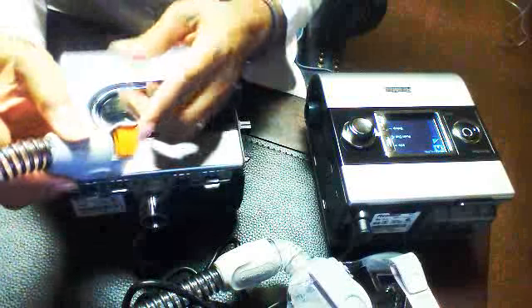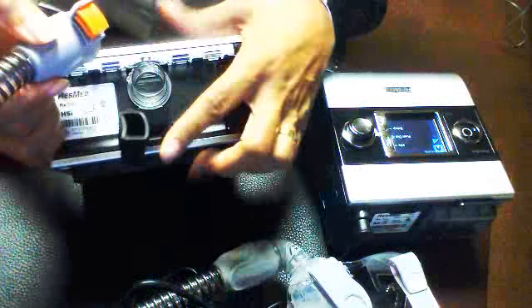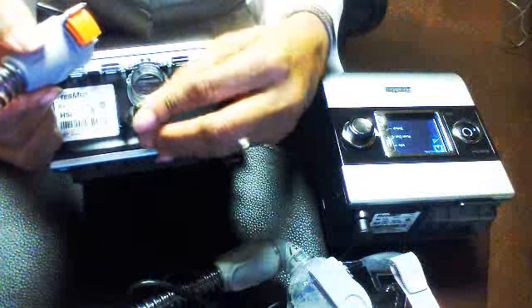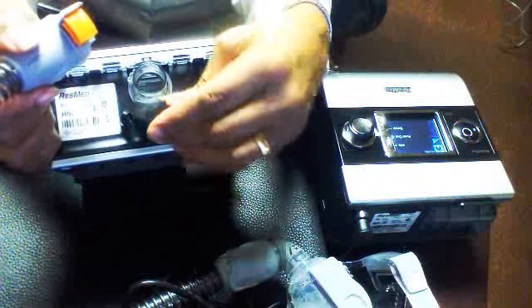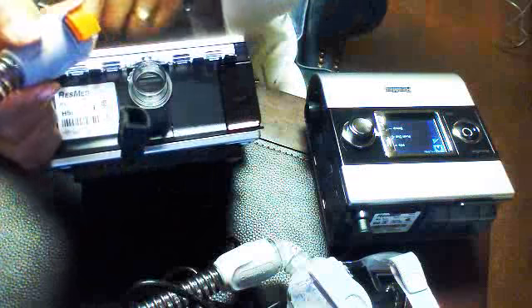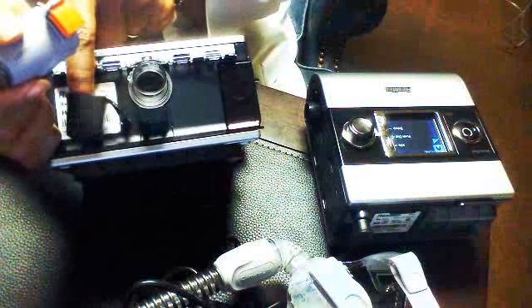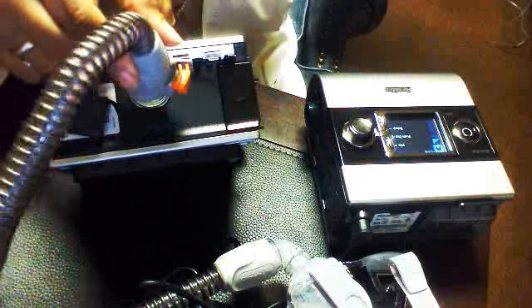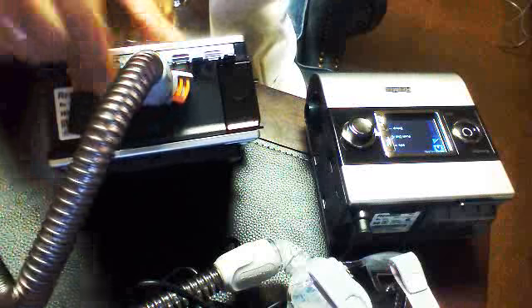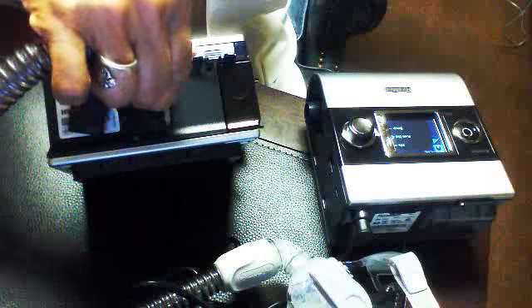This tubing has an orange lip that needs to connect to a little attachment in the back, which is also orange. You remove this cover. You don't take it off completely, just take it off of the little protruding part in the back, pop it up like this, and it stays connected by a little strap. And then you put your climate control tubing over this clear plastic tube and twist. When you hear that pop, you know that your tubing is secured and in place properly.